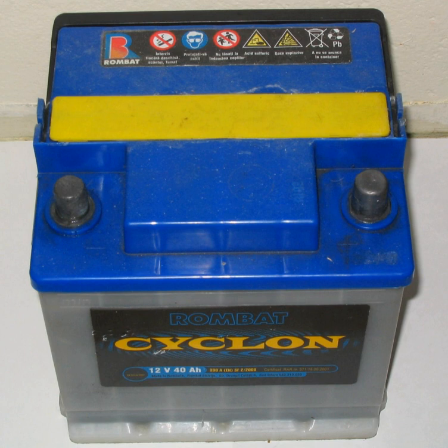The ability of gas to recombine and the benefit of a semi-saturated cell providing no substantial electrolyte leakage upon physical puncture allows the battery to be completely sealed, making them useful in portable devices. Additionally, the battery can be installed in any orientation, though if installed upside down, acid may be blown out through the overpressure vent. To reduce water loss rate, calcium is alloyed with the plates; however, gas buildup remains a problem when the battery is deeply or rapidly charged or discharged. To prevent overpressurization of the battery casing, AGM batteries include a one-way blow-off valve, and are often known as valve-regulated lead-acid, or VRLA, designs.